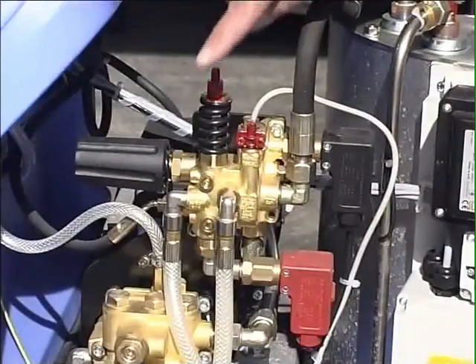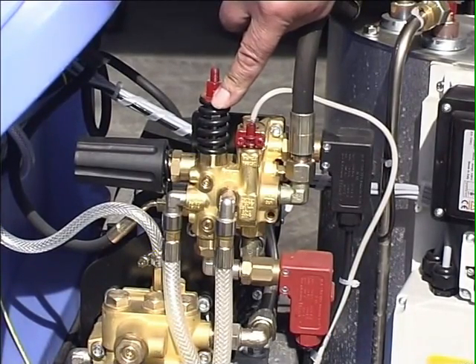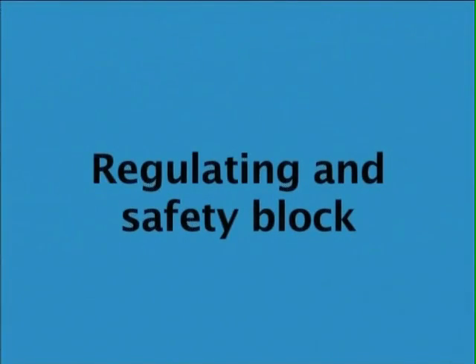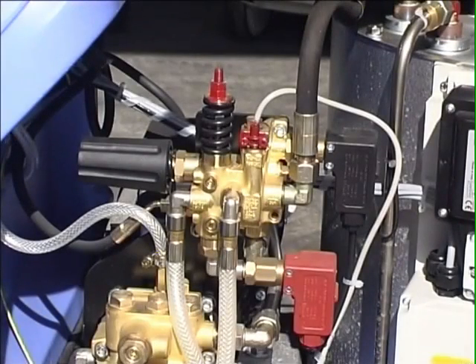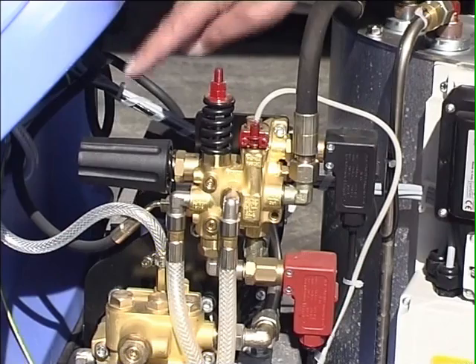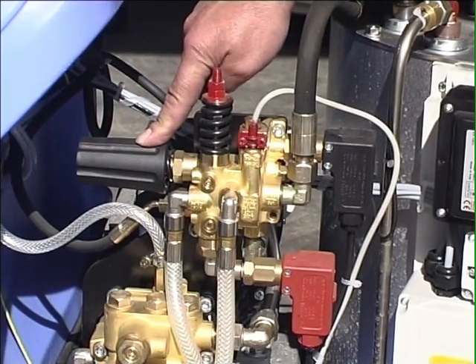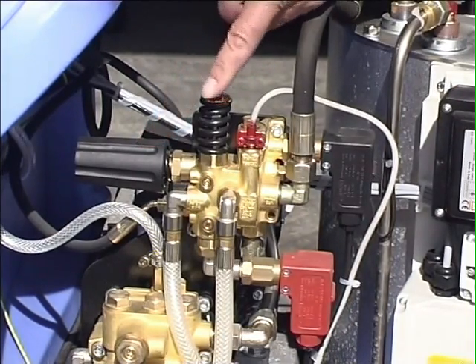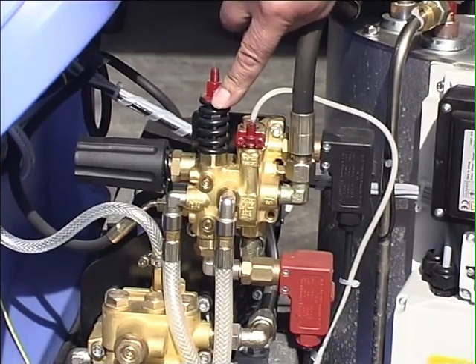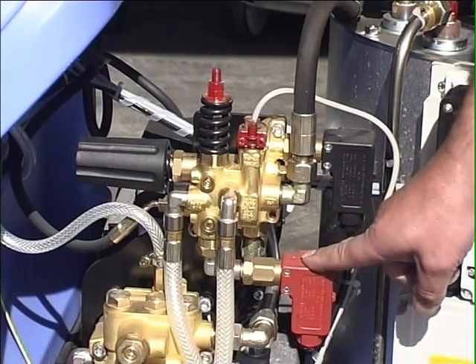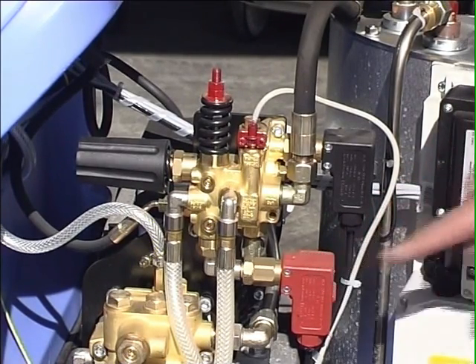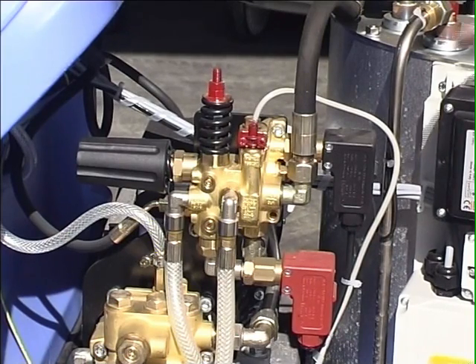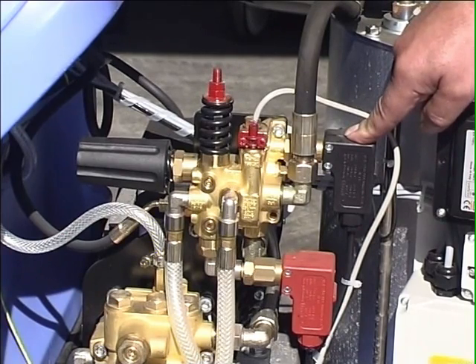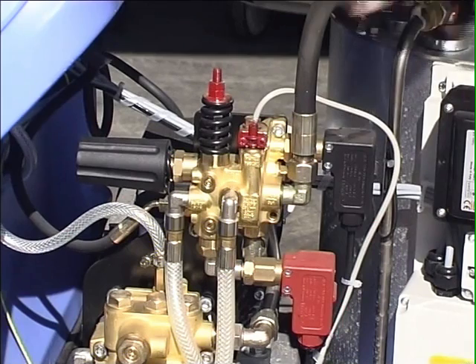The safety valve for the heating coil is here for the 5 series, and it is also set this way. In the case of the 5 series, the most important regulating and safety elements are placed in a block. It consists of 1. The unloader for pressure adjustment, which is in the pump head in the O and C series. 2. The safety valve for the heating coil, separate in case of O and C series. 3. The red pressure switch, which is on the pump head in the O and C series. 4. The black pressure switch, also on the pump head of the O and C series. 5. The flow monitor.